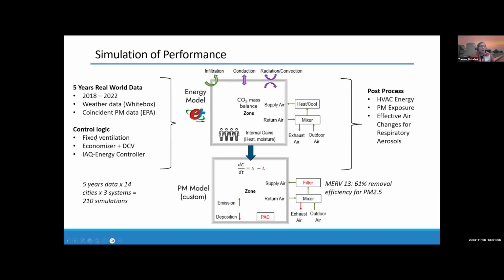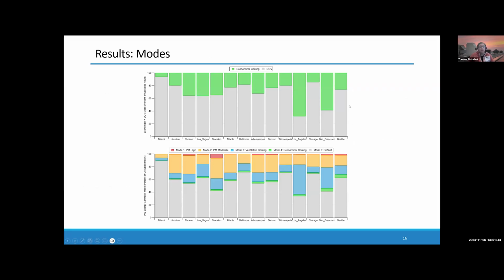And then I look at a fixed ventilation control logic, an economizer, a DCV logic, and then the IAQ energy controller. At the end, we're looking at HVAC energy, how much HVAC energy is consumed according to the model, the PM 2.5 exposure for those people inside, and the effective air changes per hour for respiratory aerosol removal. And I don't think I've stated it, but I'm looking at a classroom environment in these scenarios because classrooms are essentially one of the biggest challenges because of all those densely occupied bodies. Also, children are very sensitive to PM 2.5 exposure.